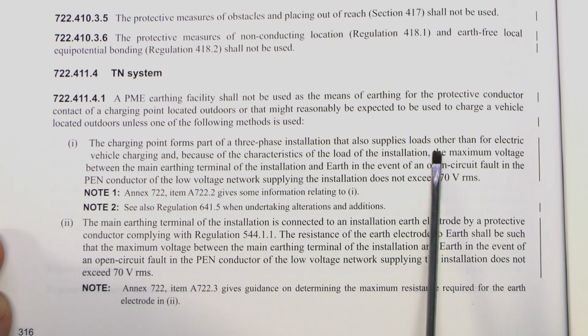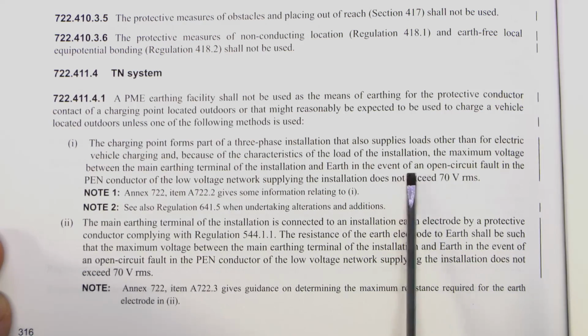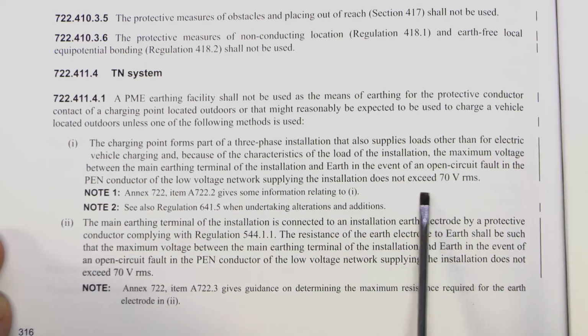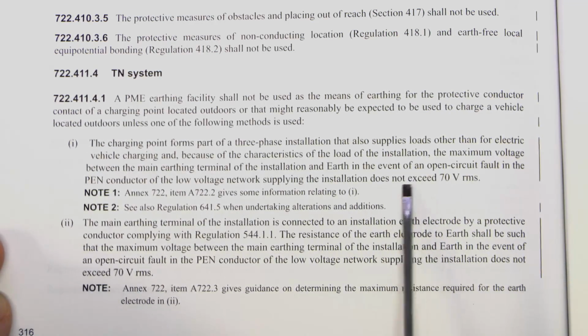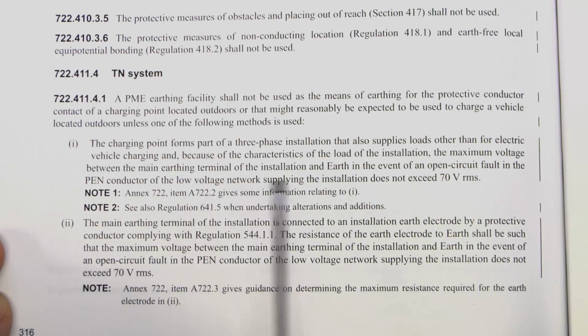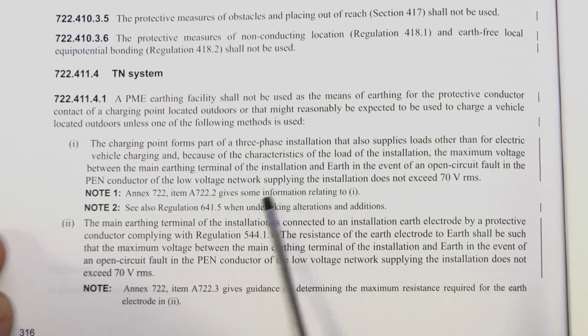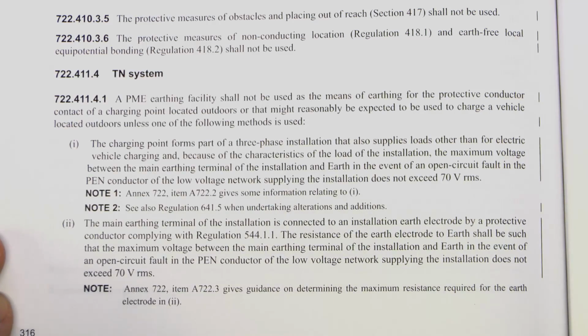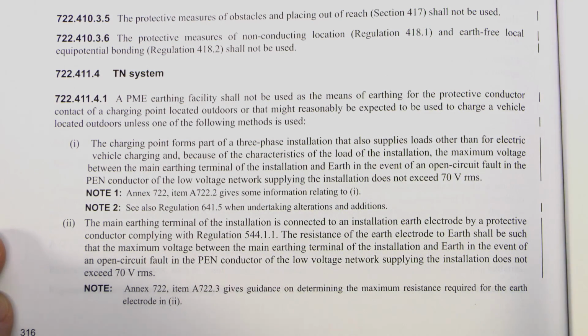The type of loads it's referring to are where it's a 3-phase load and it's a balanced load, which means that the current in the neutral essentially would be 0 or close to 0, and of course that would then result in pretty much no voltage showing on that if the PEN conductor, of course the neutral and earth combined, is disconnected. So there is no way you're going to be using that on a domestic installation, but of course it could apply to more industrial or commercial areas.